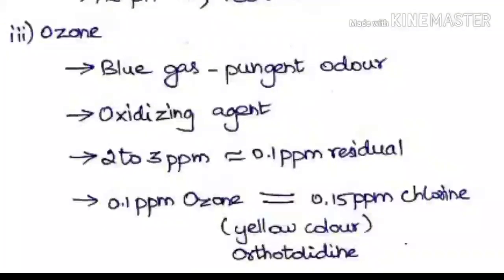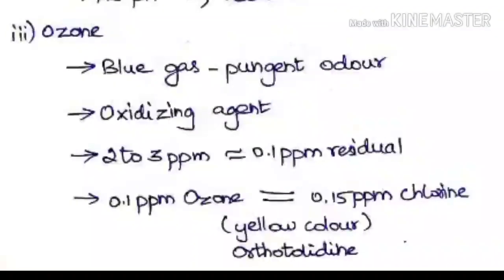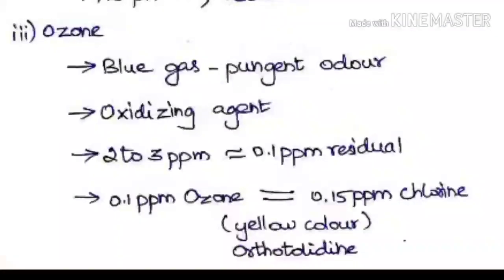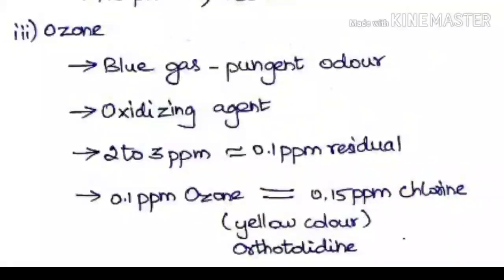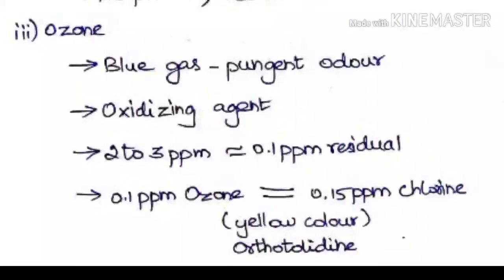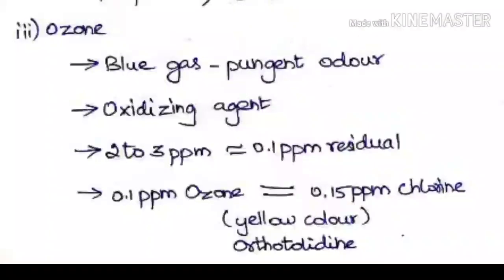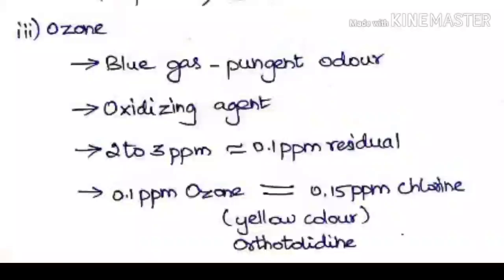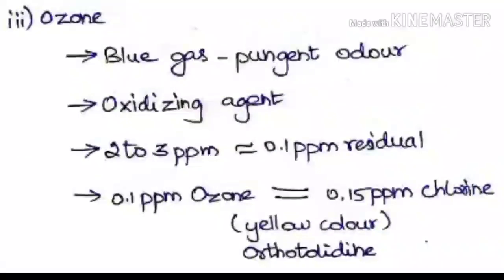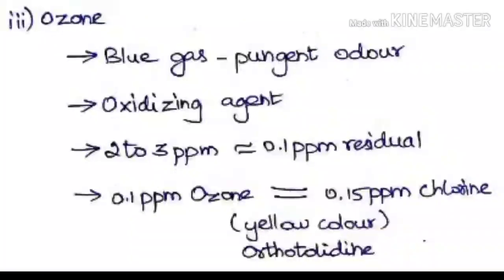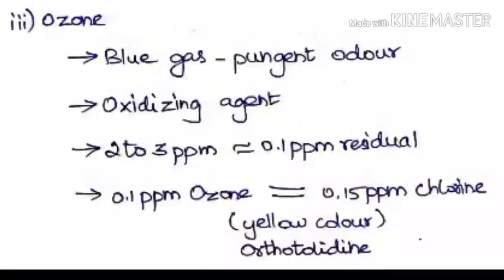Ozone is a great oxidizing agent. If we use nearly 2 to 3 ppm, it will have a residual of nearly 0.1 ppm. When this residue remains in the water it will be a preventive measure for disinfection even in the distribution system. 0.1 ppm ozone is nearly equal to the effect of 0.15 ppm chlorine, so the intensity of the yellow color visible in the orthotolidine test will be the same for both.